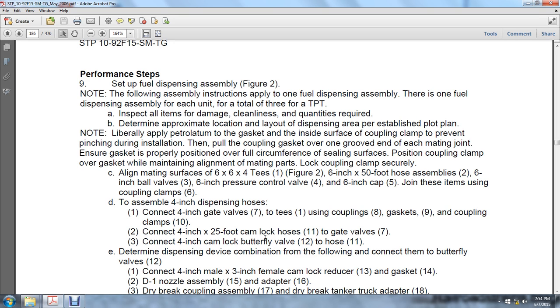Line up the mounted mating surface of the 6x6x4 inch tees (1), figure 2, 6-inch x 50-foot hose assemblies (2), 6-inch ball valves (3), 6-inch pressure valves (4), and 6-inch caps (5), and join the items using the coupling clamps. To assemble the 4-inch dispensing hose, connect the 4-inch gate valve (7) to the 2 tees (1) using couplings (8), gaskets (9), and coupling clamps (10).